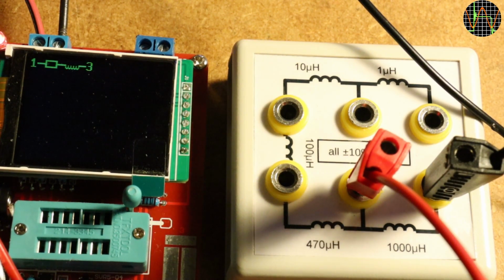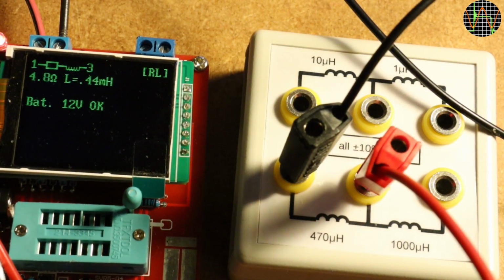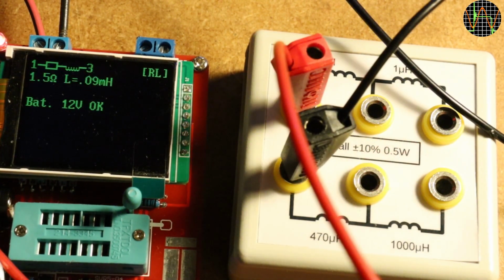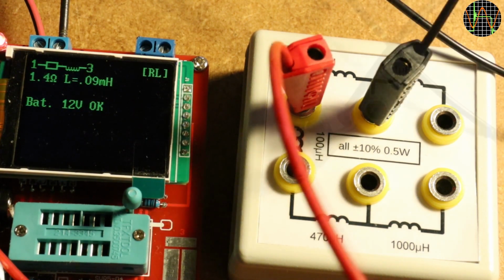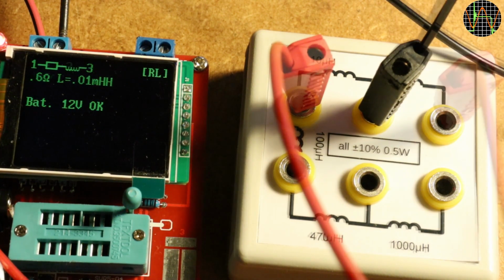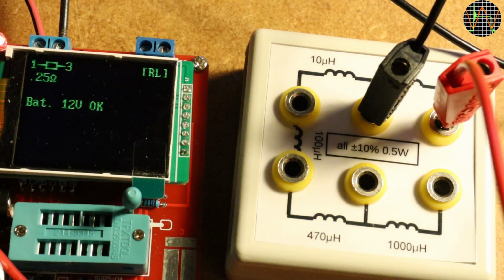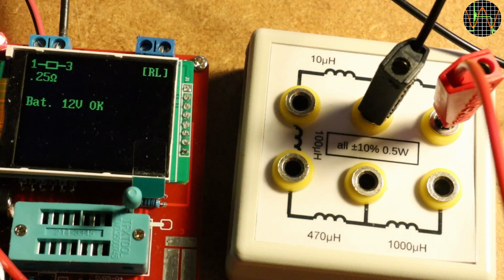It selected automatically the RL mode and shows 1.05 millihenry or 1050 microhenry. It shows 0.44 millihenry, and nearly at its limits it shows 90 microhenry for 100 microhenry and 10 microhenry for 10 microhenry, but this is really the lowest possible value it can measure. Yes, it does not recognize 1 microhenry as an inductor and shows only the resistance value.